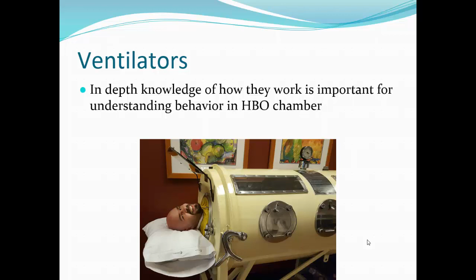And this is a picture of Dan Popa, one of my coworkers at UCSD, and they actually had an iron lung like in the cafeteria over there. So in an ideal world, an ideal ventilator would have minimal electrical requirement. This is one of the arms of your fire triangle: oxygen, heat source, which is your electrical requirement, and then the fodder, or the fuel for the fire. You want to have ventilators that have low oxygen bleed into the environment, because if you start contaminating in a multi-place center, pumping in more than 24% FiO2 into that chamber environment, the risk of fire goes incrementally up.